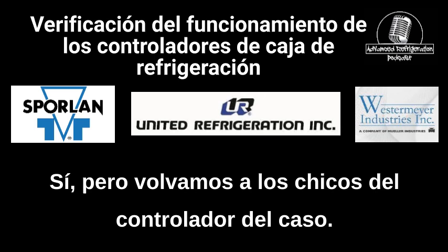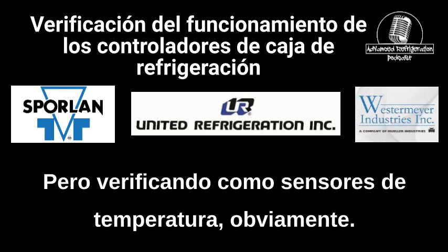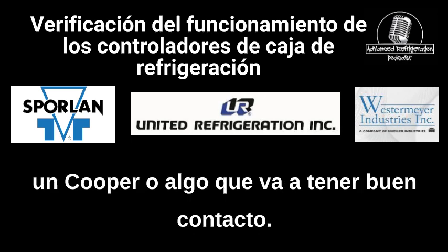But back to the case controller, guys. Verifying temp sensors: obviously make sure the pipe's clean, and then check it with something like a Cooper that's going to have good contact.